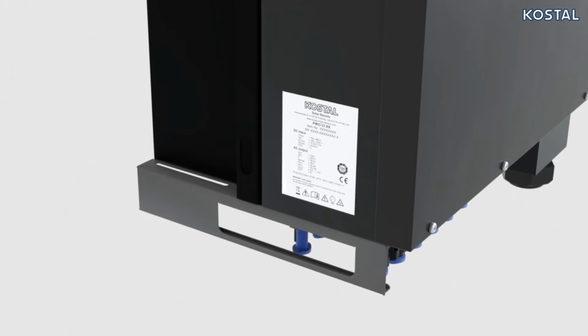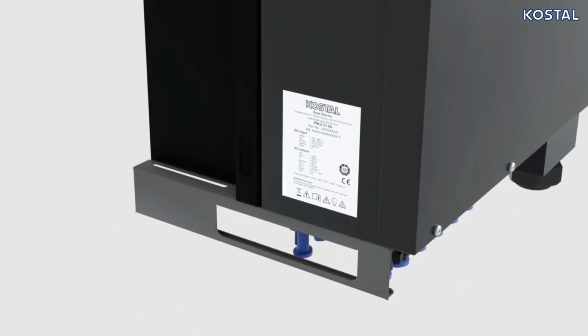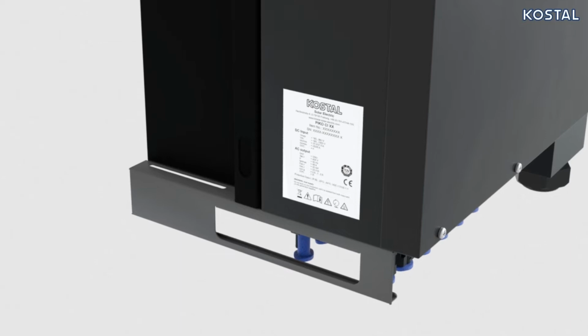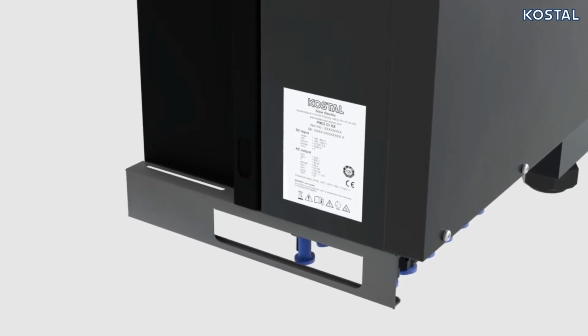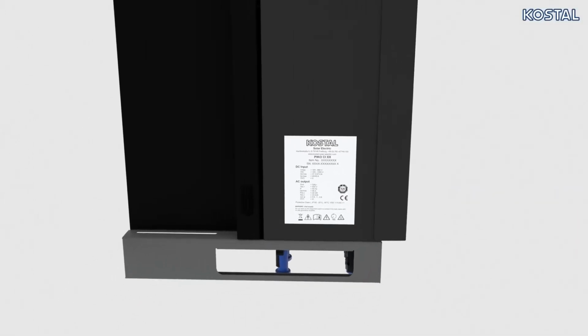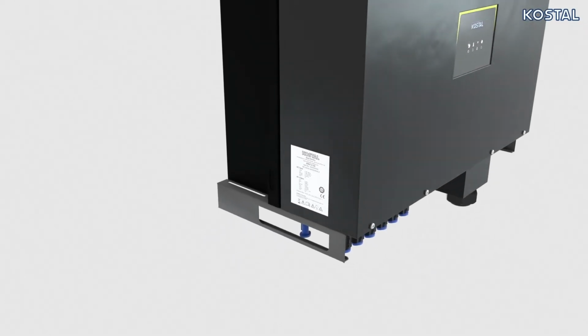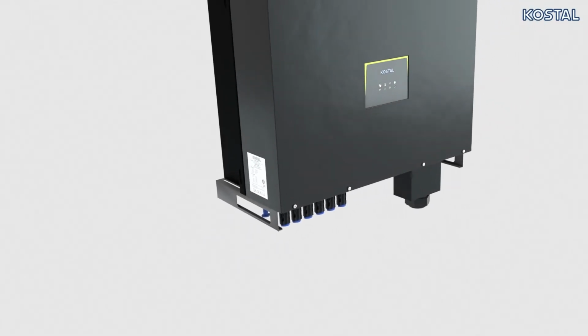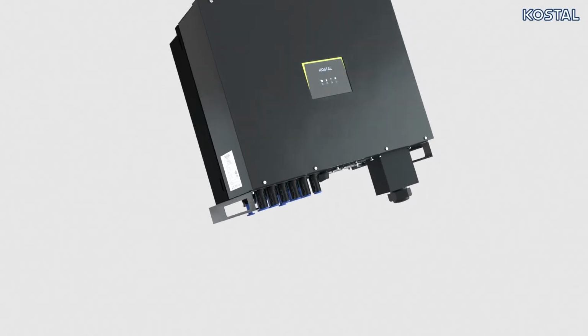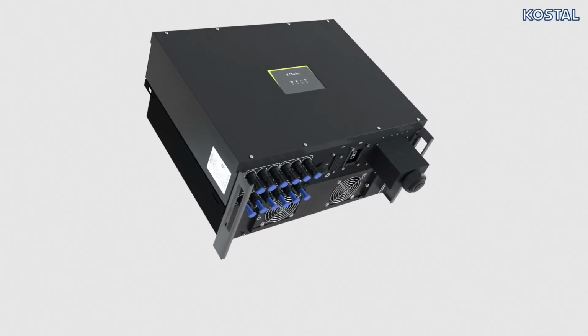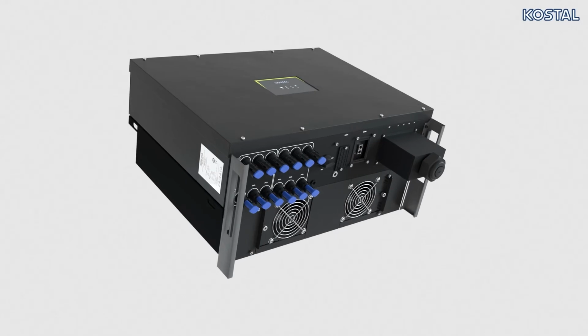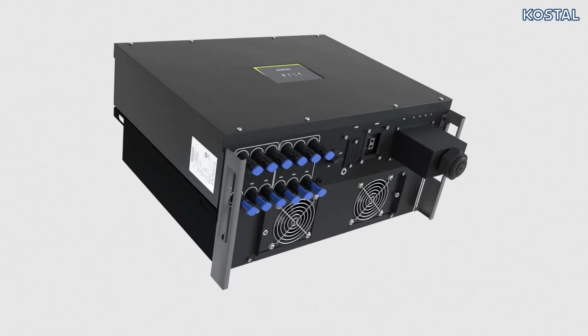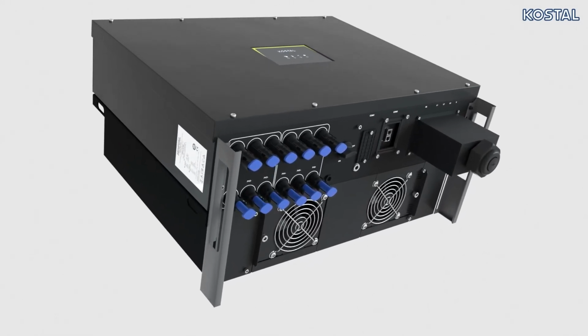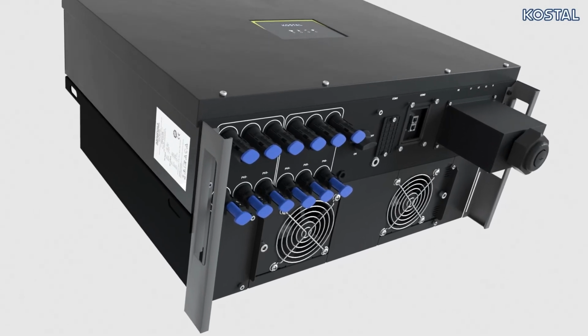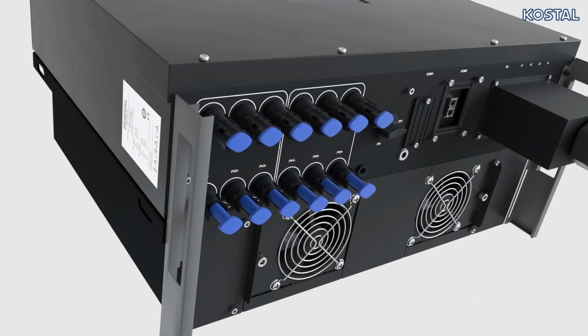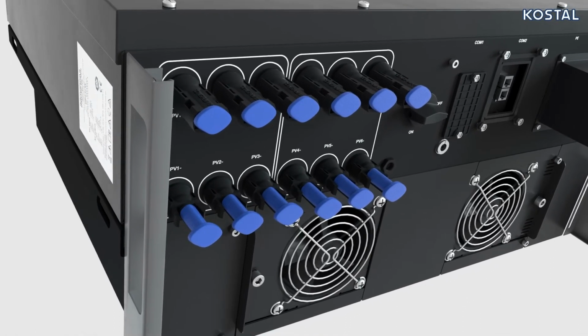The type plate on the left side of the inverter contains the serial number, technical details, and warnings. The connection area can be found on the underside of the housing. The device provides various interfaces for connecting to other inverters, sensors, energy meters, or the internet. Up to 6 DC connections are provided to connect the PV generators. To make these connections, use the pair of Amphenol H4 connectors provided with the corresponding contacts.